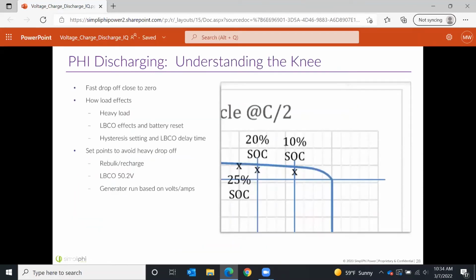All right, and another important thing about discharging is understanding that knee. So we talked about how after 20% state of charge, the voltage does begin to more rapidly decrease. Once you hit 48 volts, and you'll notice it's very stable as you're approaching that 48 volts, but once you hit it, man, does it drop off fast. It's like it hit a cliff and jumped right off. It just is very quickly declining in voltage after that. And then you're drawing more current because the voltage is lower, and it just gets worse and worse.